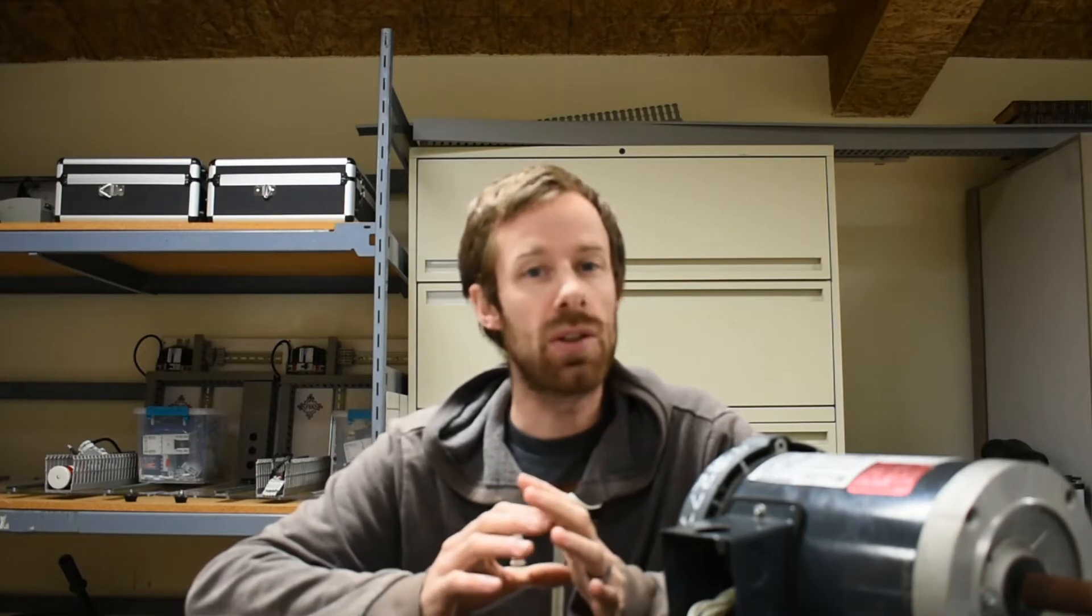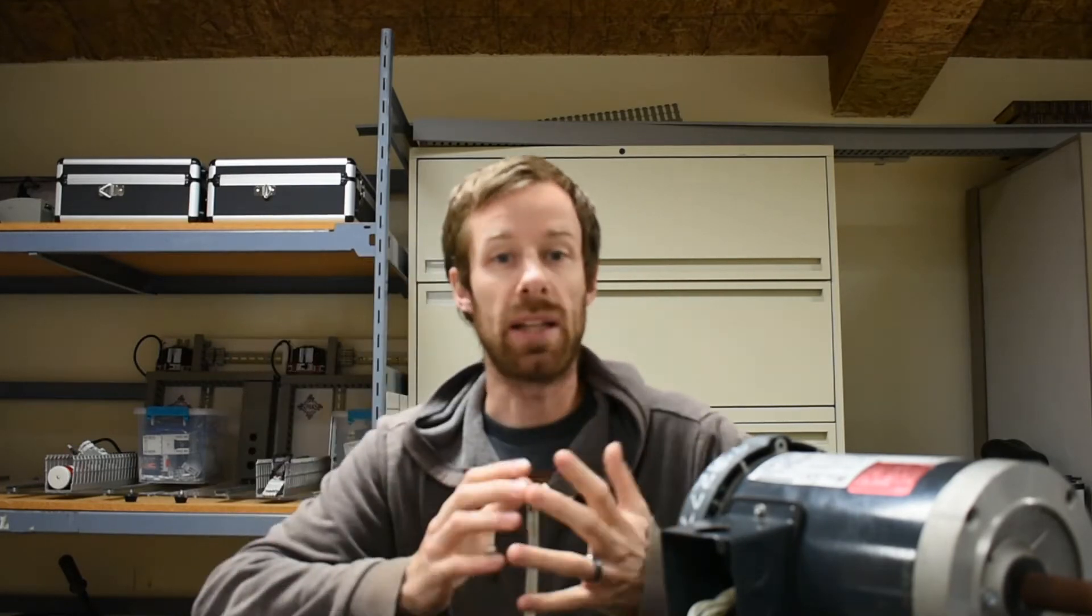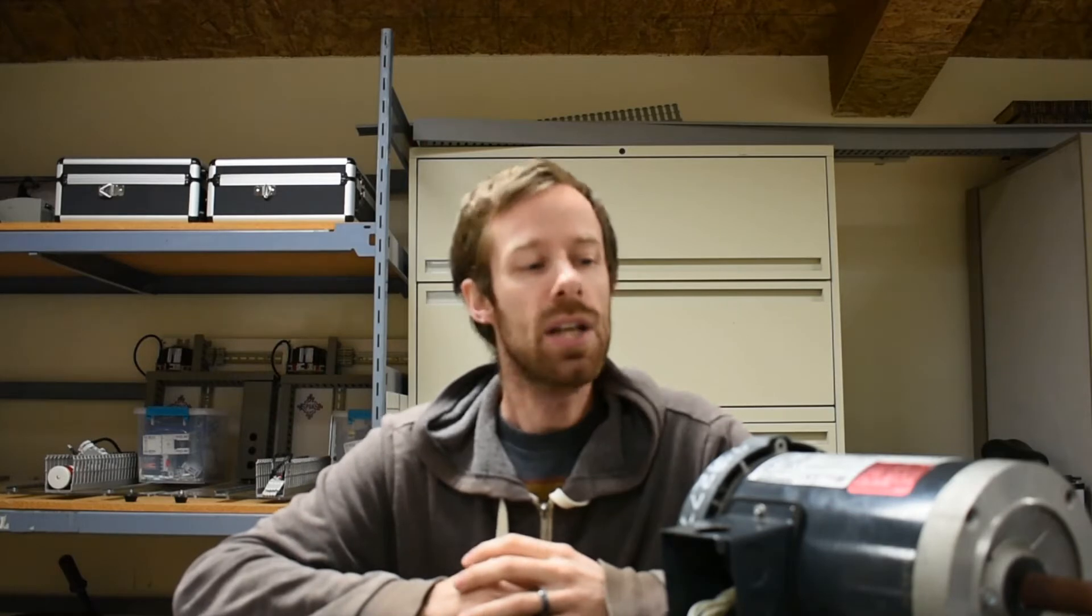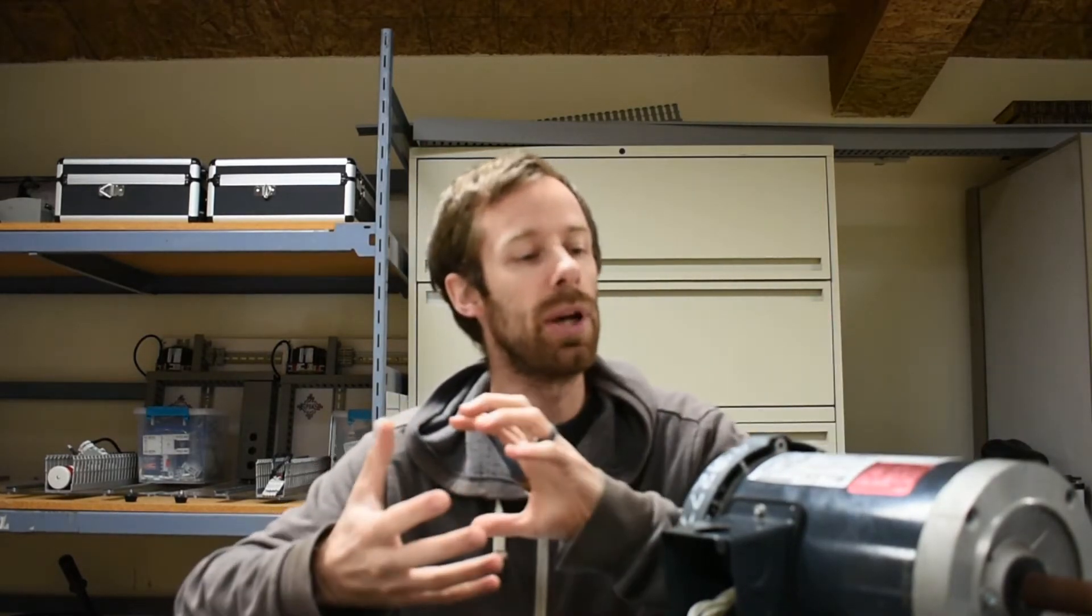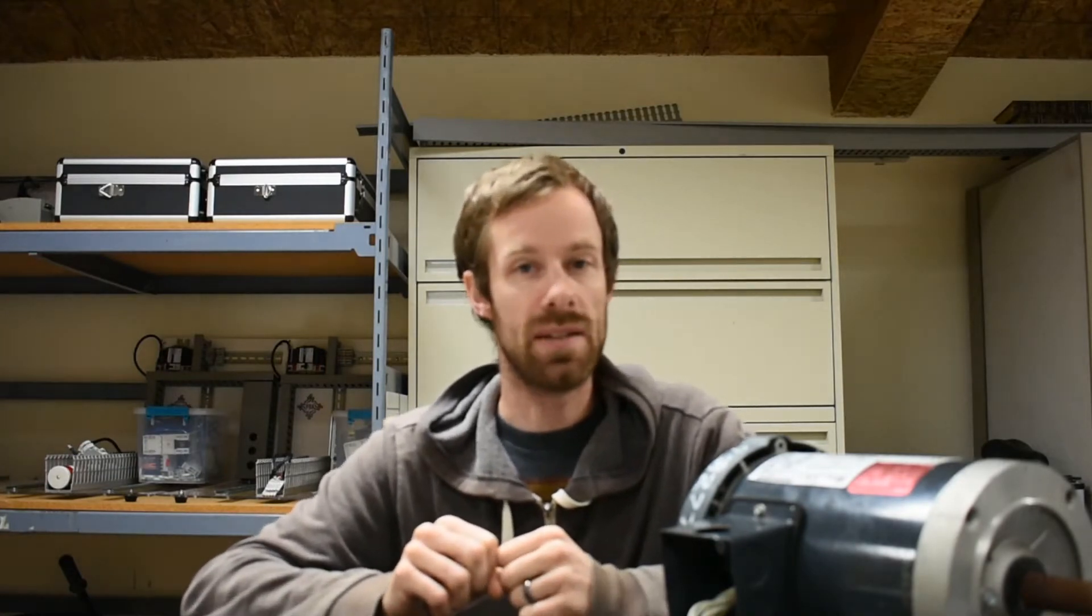Most of them are wound with what they call a Y-winding inside, W-Y-E, and that it refers to not a physical arrangement of how the coils are arranged inside. They're not physically pointed in an upside-down Y shape like the diagram sometimes show, but rather electrically how they're connected. So I'll show you a little bit about the data plate and the sticker and what you can expect to see on these things, and then we'll look at a breakdown of how the coils are arranged inside.